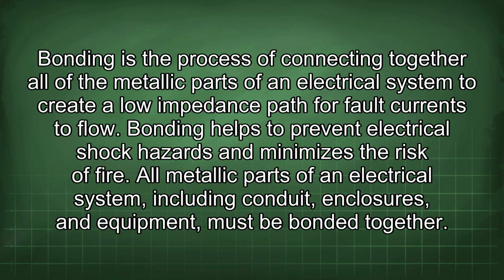Bonding is the process of connecting together all of the metallic parts of an electrical system to create a low impedance path for fault currents to flow. Bonding helps to prevent electrical shock hazards and minimizes the risk of fire. All metallic parts of an electrical system, including conduit, enclosures, and equipment, must be bonded together.